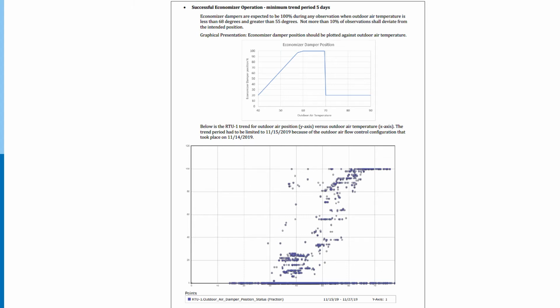And then what you see down at the bottom is the real data. And a couple things. Notice the big block of points down on the x-axis. That's the 0 point. And in particular, if you look between 60 and 70 degrees, those are all the hours when the economizer is supposed to be working, but it's not opening. It's closed when it should be open. So we're not getting the energy savings that we want to be getting. The commissioning team did not quantify that, but I'm guessing that they didn't meet the 90% threshold here.